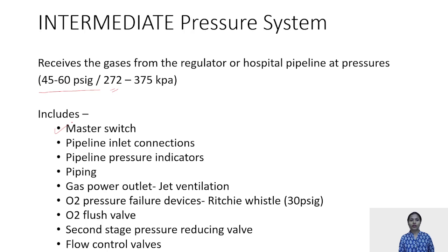It includes your master switch. Master switch, I had told you in your previous class, this is the switch which is responsible for the switch on of your electrical as well as pneumatic component. And in the whole of the anesthesia machine, please remember, there is just one thing which is independent of your master switch, whether the master switch is on or off. It only requires that a supply of oxygen should be connected to your machine, and that's your oxygen flush. Your oxygen flush will always be activated, and it is independent of your master switch.